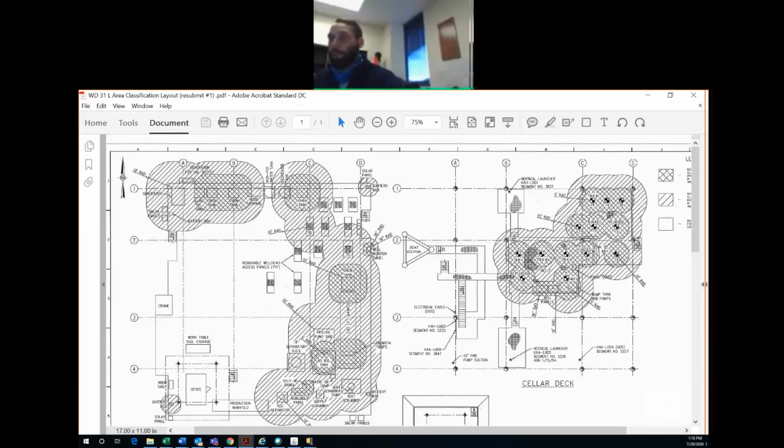So this became very useful, and that's why you'll see it more on drilling rigs, which have missions overseas and then will have missions in the Gulf. So it's more advantageous and it makes more sense for sometimes a drilling rig or a FPSO to classify their system using API 505, which again would use zones instead of divisions. And the key difference is that there are 3 zones ranging from gas most likely being present to gas least likely being present, zone 0, zone 1, and zone 2.